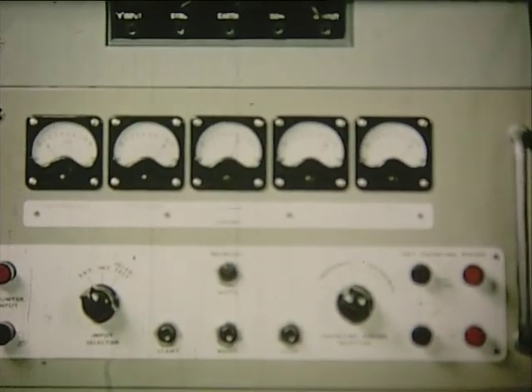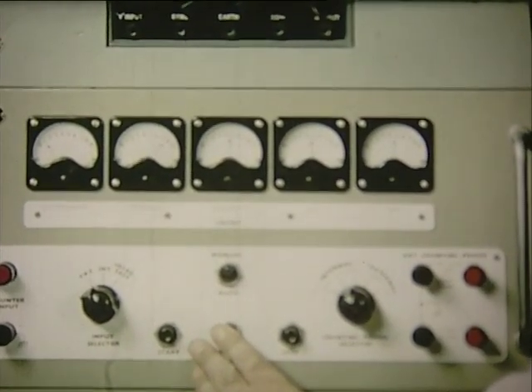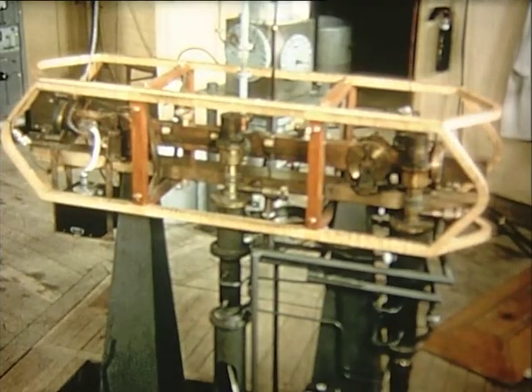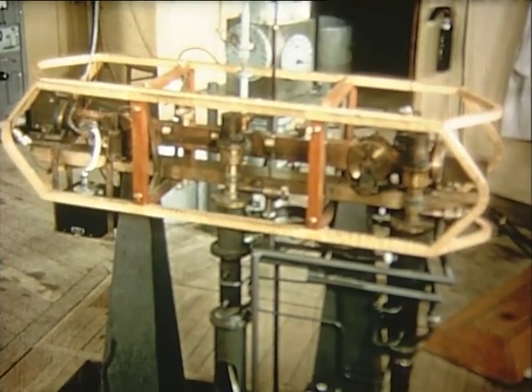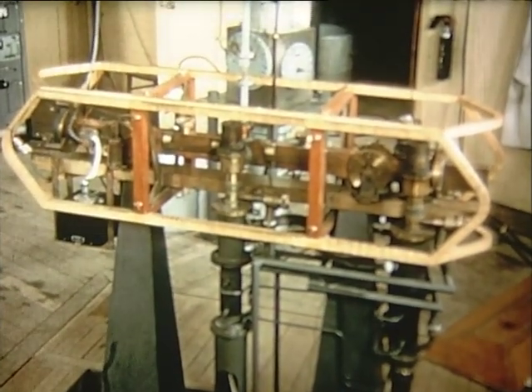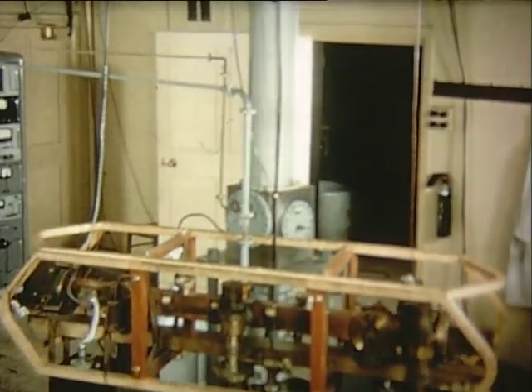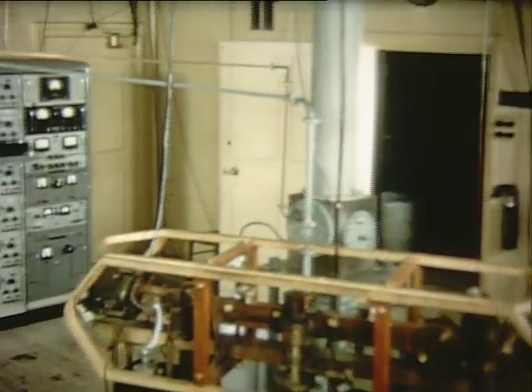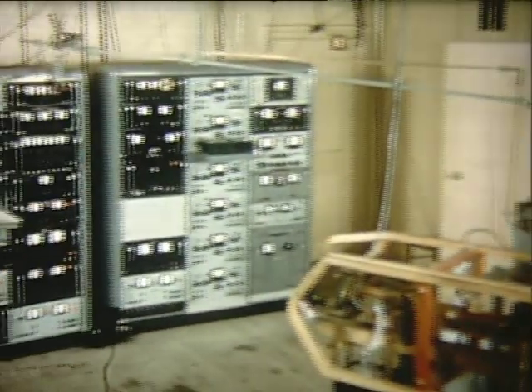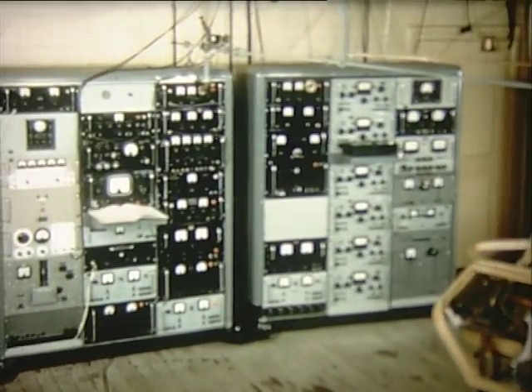A button is pressed, and the dial readings give the error of the working standard. A complete measurement takes a few minutes, and the result is accurate to one part in 10,000 million. The precision of an atomic clock is most easily increased by making the atoms travel further.